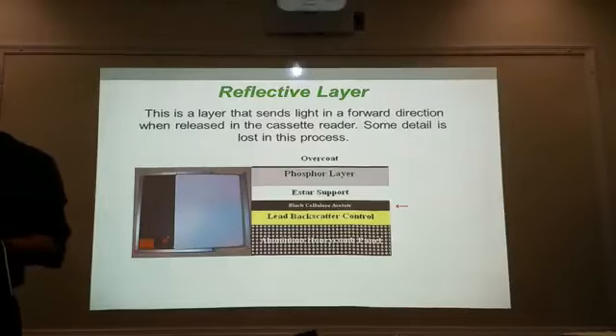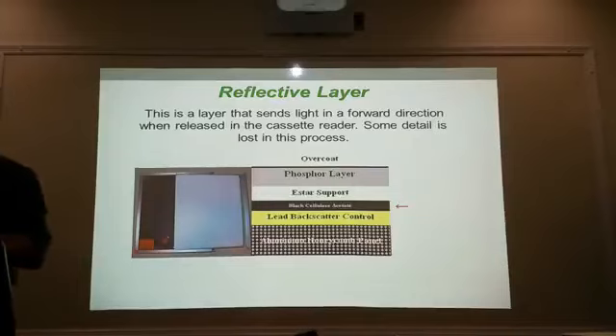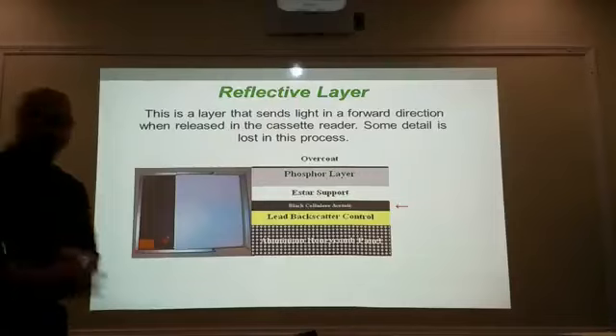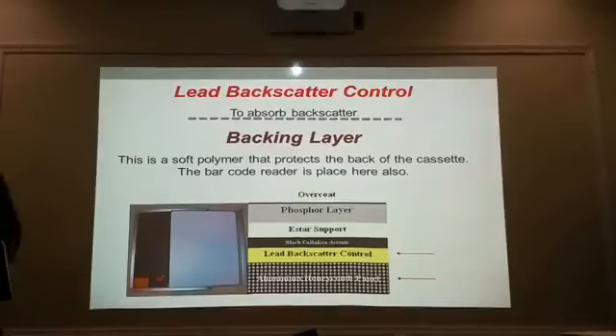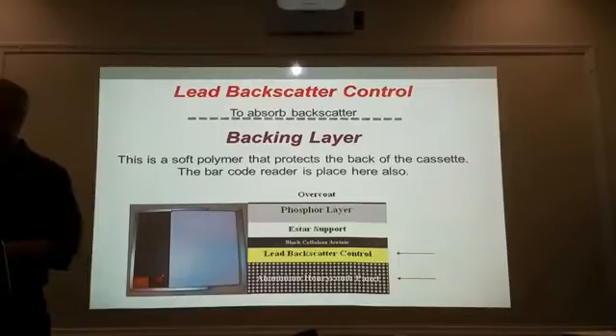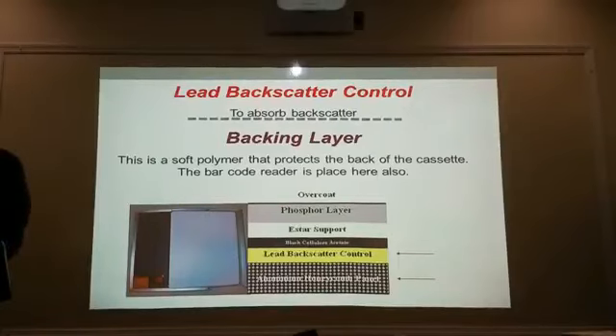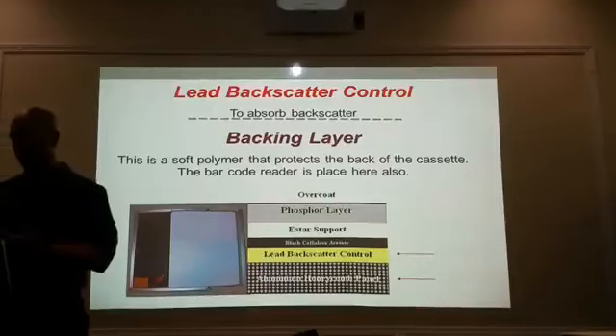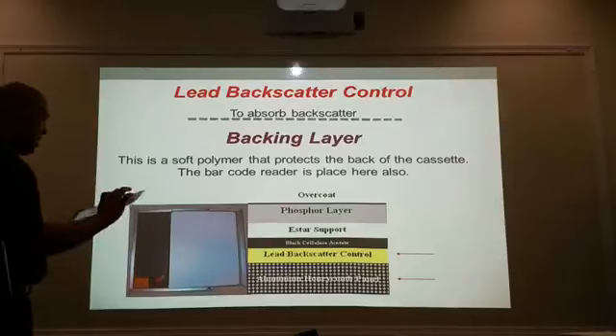The images that come up on the display screen are so detailed, so nice — it's unmatched compared to film. The last two layers: you've got the lead backscatter layer to control any backscatter, and then the backing layer — a soft polymer in the back of the cassette that also supports the PSP.